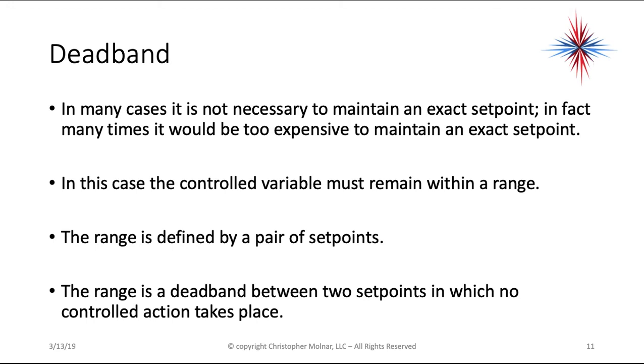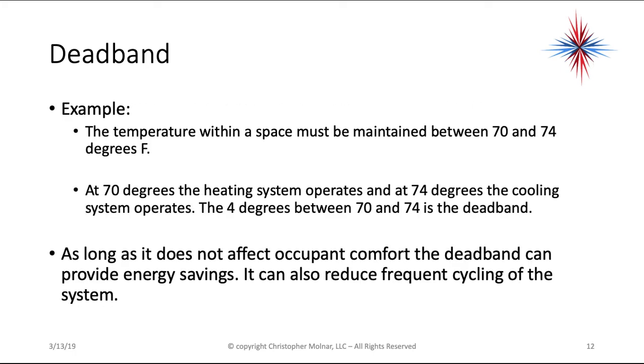Dead band is another measurement. In many cases it's not necessary — or even too expensive — to maintain an exact set point. Instead, the controlled variable must remain within a range defined by a pair of set points. The dead band is the range between two set points in which no control action takes place. For example, temperature must be maintained between 70 and 74 degrees: at 70 the heating operates, at 74 the cooling operates — the 4 degrees between them is the dead band. This reduces frequent cycling and can provide energy savings.